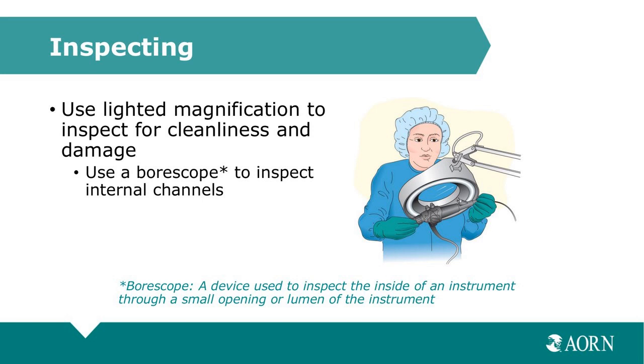After manual cleaning, flexible endoscopes and their accessories should be inspected for cleanliness and for damage. And we recommend that this inspection takes place using lighted magnification so you can see what you're looking at. You can inspect the internal channels of flexible endoscopes using an endoscopic camera or a borescope.